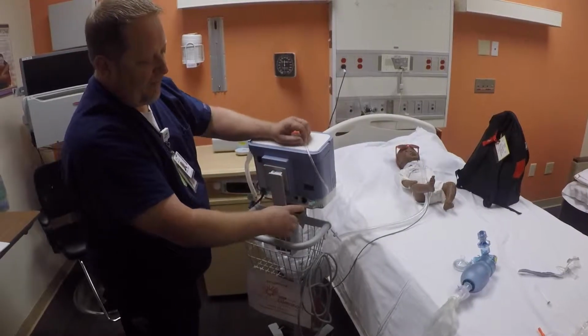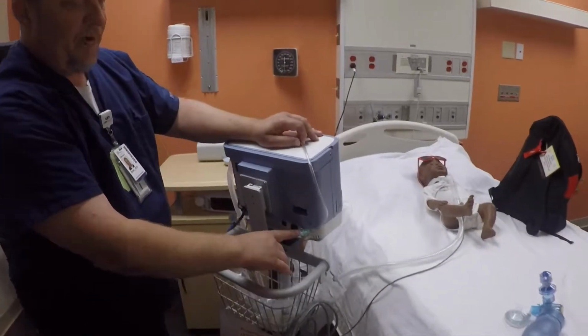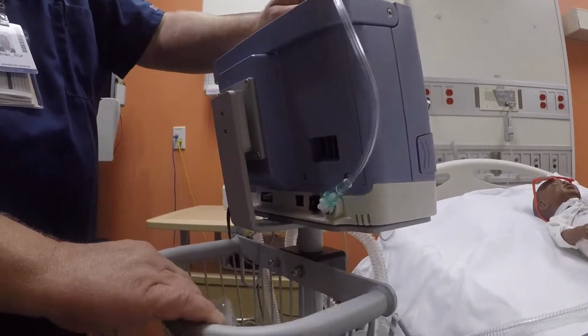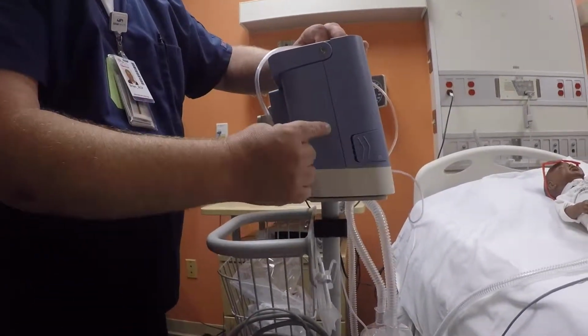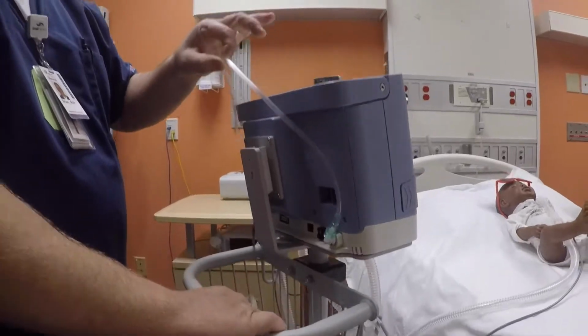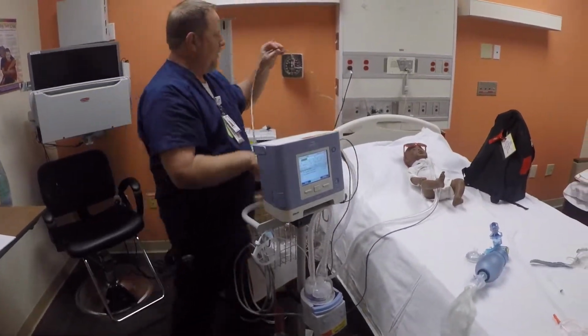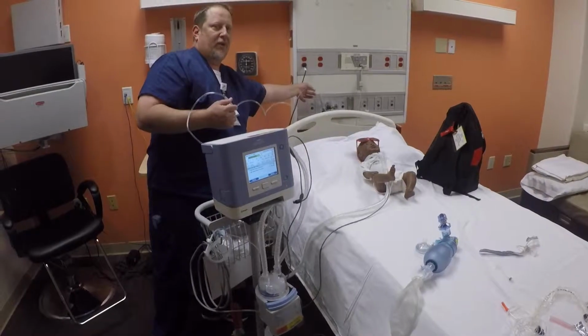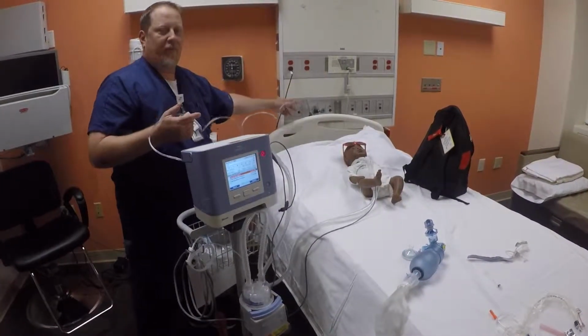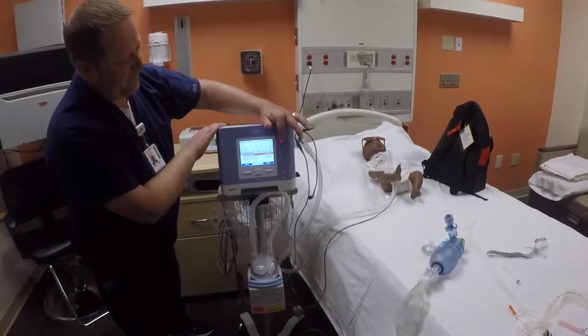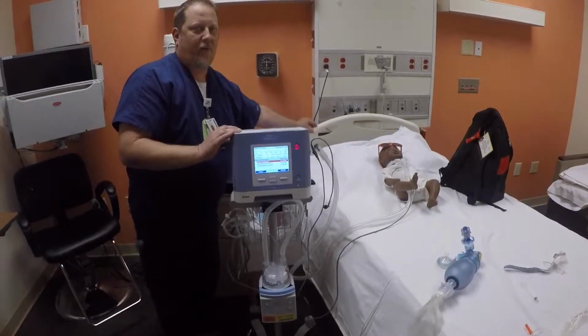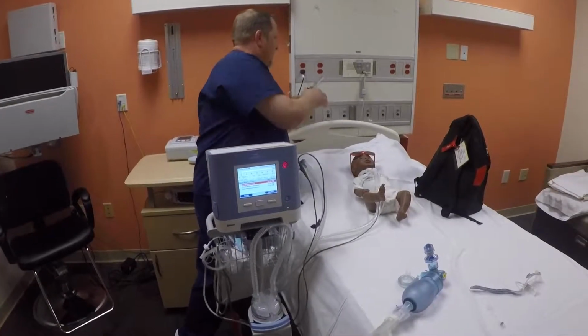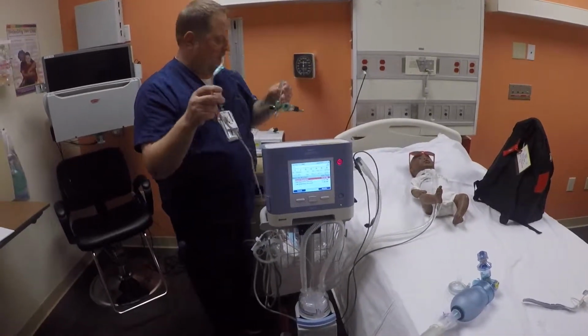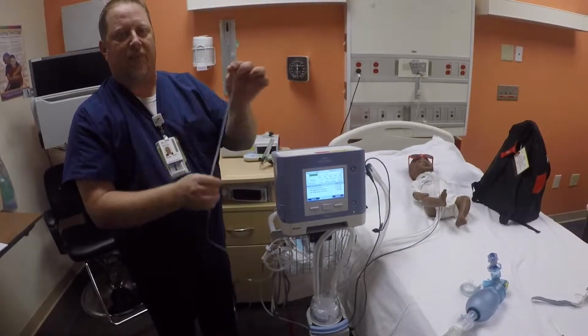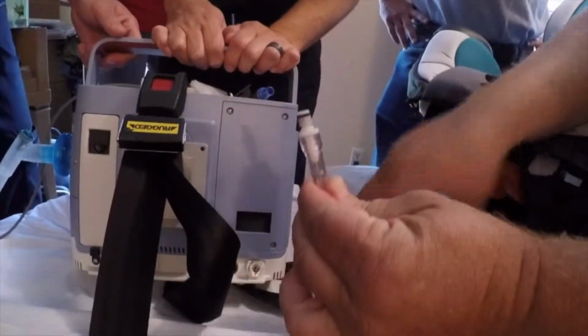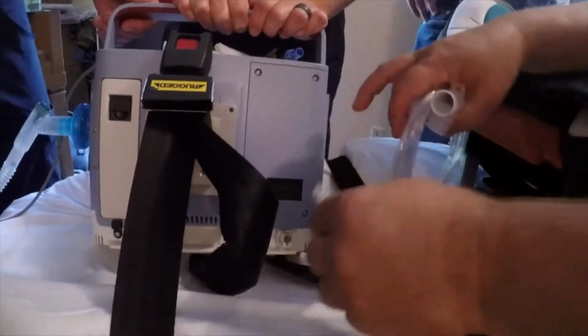All home ventilators will have an oxygen port of some type. It could be in the back of the machine, or sometimes it's on the side of the machine. This will just use your standard oxygen flow meter. It might be on a concentrator at home, but for EMS, we are just going to take that off, and we'll hook it straight up to our E or D tank and set it at the same flow that the parents were doing. This can break off, just the position it's at can break.